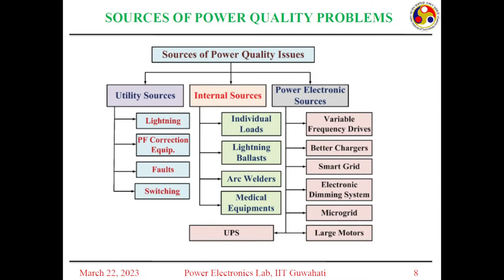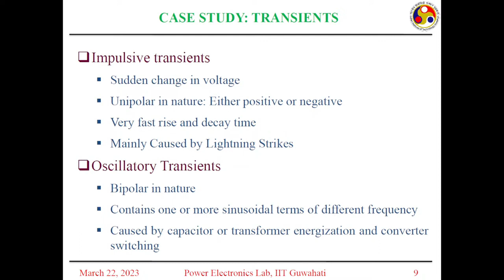What are transients, what are harmonics, and how does unbalance happen? For example, if you consider an impulsive transient or an oscillatory transient, there is a difference between the two. An impulsive transient is unipolar in nature; it can be either positive or negative. An oscillatory transient is bipolar in nature, and there will be 2-3 sinusoidal terms with different frequencies. Impulsive transients are caused by lightning strikes, and oscillatory transients are caused by transformer or induction motor energization.